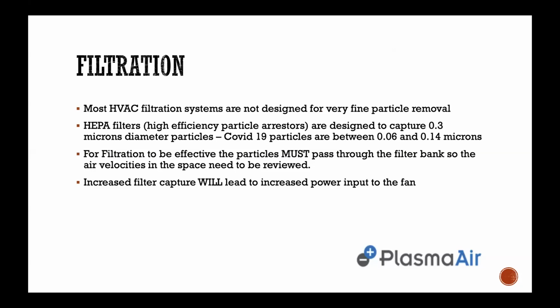HEPA filters, which are designed for high efficiency particle arrestment, have very high pressure drops. Existing systems, in most cases, are not designed for these very high pressure drops. So we have to be very careful when looking at putting filtration in, as to how the system will perform when we retrofit with the filtration systems we need now.